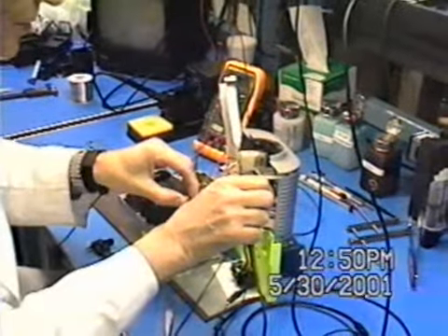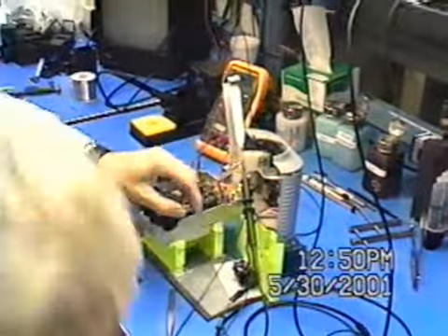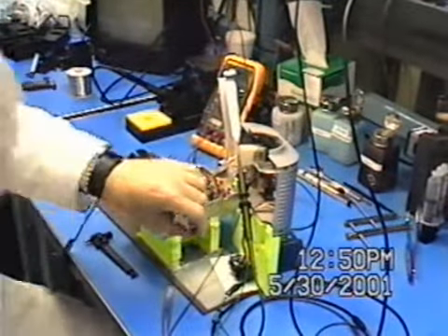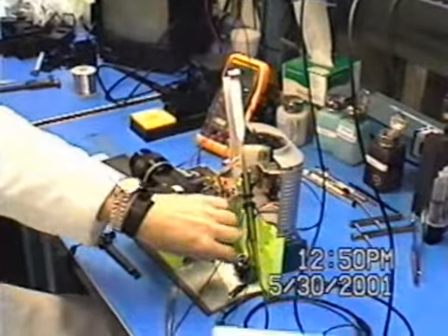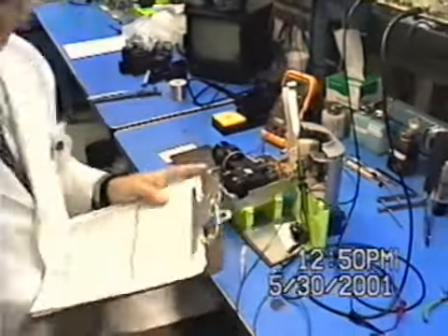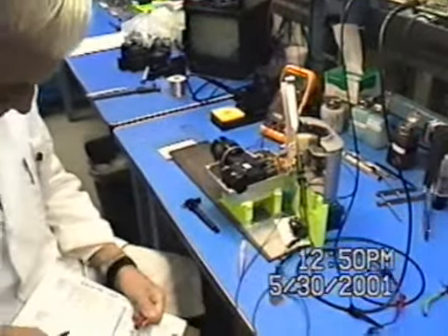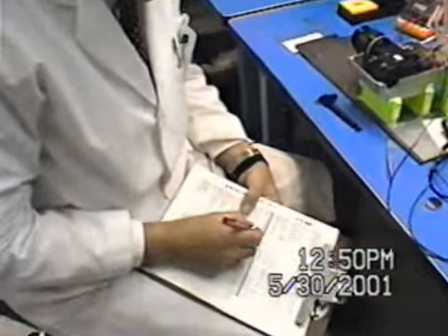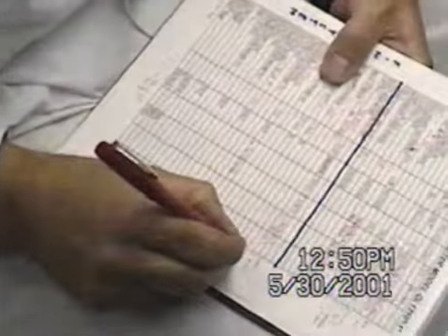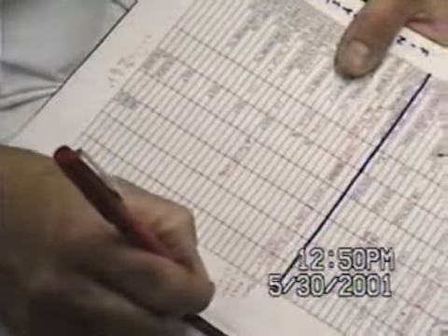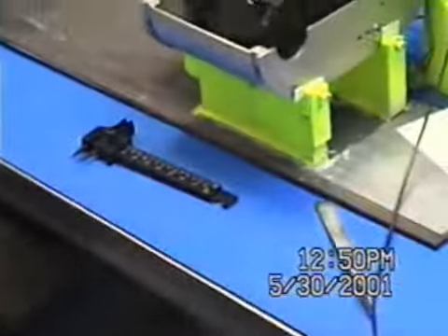We're going to get that prism tomorrow or the day after. 1655. I can actually see it from here. 1655 is what it reads, okay? Of course, we're going to go on a computer to calculate that one. That's okay. So now, with 3.3 megaohm, wall temperature is 1655 Fahrenheit. Let me just quickly convert that into centigrade.